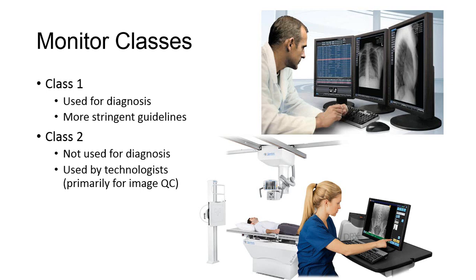It's important to distinguish between two classes of monitors used in medical imaging in order to properly evaluate acceptable standards. Class 1 display monitors are used for diagnosis and have more stringent guidelines for QC than Class 2 monitors — these would include the radiologist workstations. Class 2 monitors are not used for diagnosis, and only baselines for image brightness, contrast, and resolution need to be logged using the SMPTE test pattern. These would include most technologist workstations.